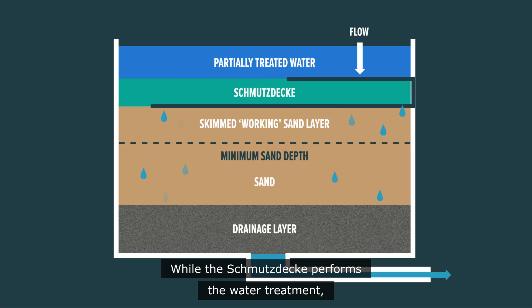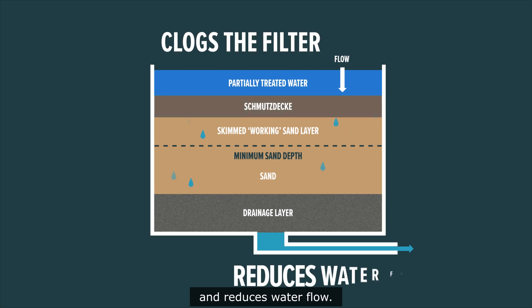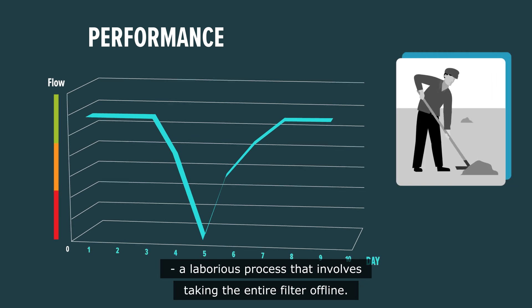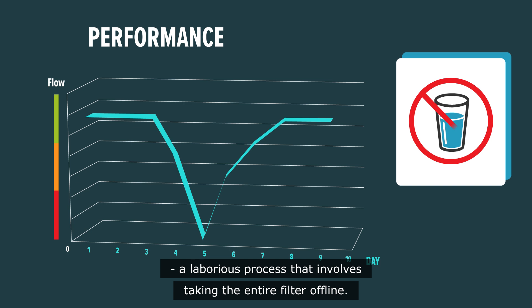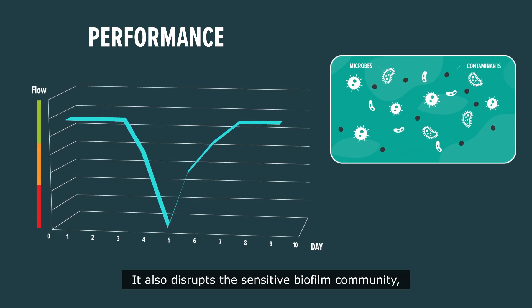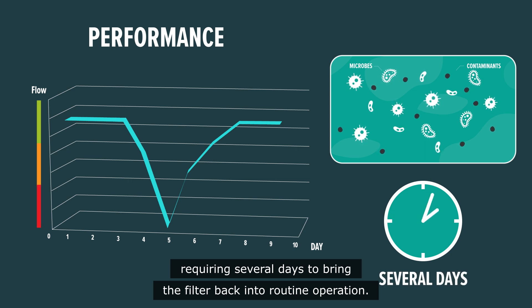While the Schmutzdecke performs the water treatment, it also slowly clogs the filter and reduces water flow. Traditionally, this problem has been managed by draining and manually cleaning the sandbeds, a laborious process that involves taking the entire filter offline. It also disrupts the sensitive biofilm community, requiring several days to bring the filter back into routine operation.